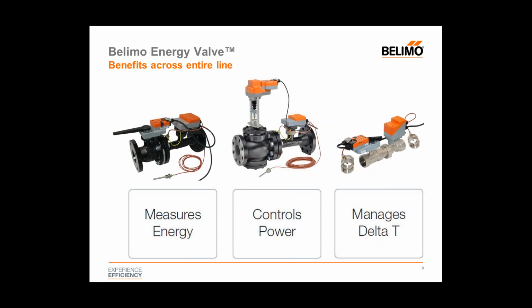Another thing it can be used for is diagnostics. Let's say a coil was cleaned and they want to ensure that they get an improvement in performance. They can run the energy valve prior to cleaning the coil or repairs made on the coil, and run it after to see if the improvements, the BTU increase and delta T increase that they were looking for, are actually achieved. I'm going to talk a little bit more in the next slide about how we can look at some of that data after it's been stored.